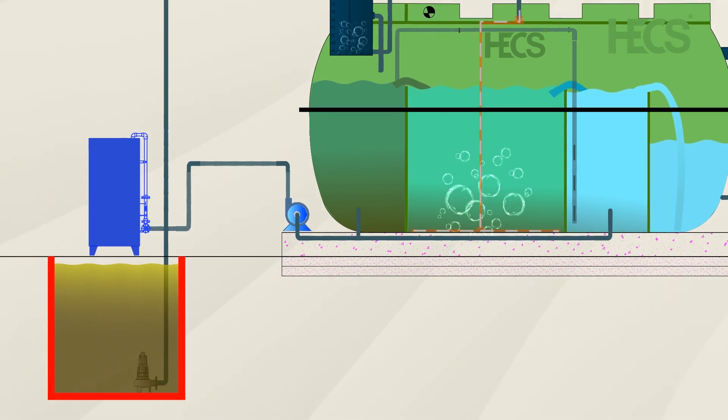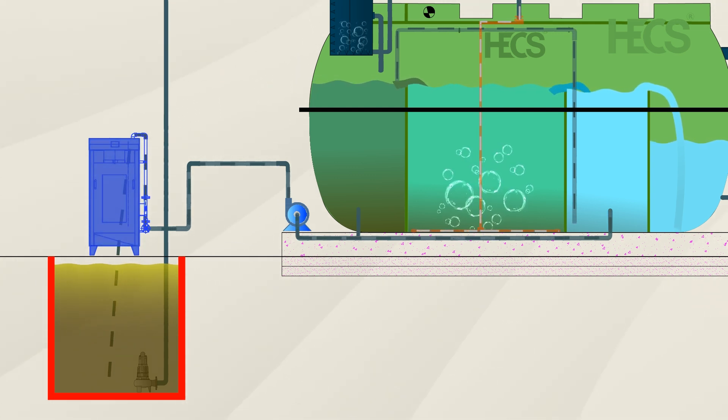Sludge management is streamlined within our plant. An internal recirculation system significantly minimizes sludge formation. Excess sludge is periodically transferred into a sludge bag filter, where the separated water is efficiently returned to the collection tank, completing a full cycle of sustainability.